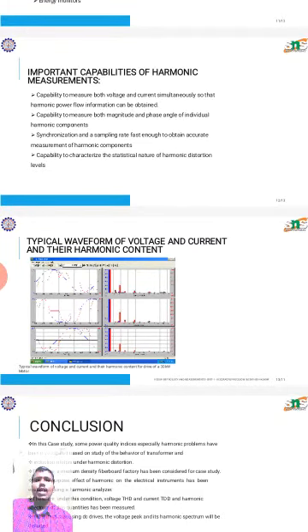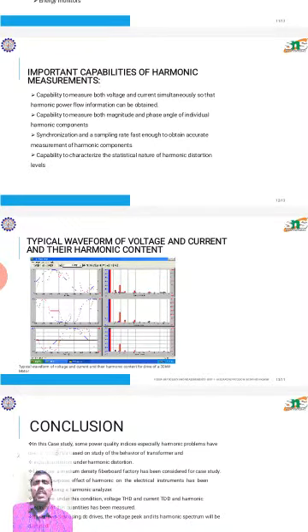So THD means the total harmonic distortion of voltage, and TDD is the total demand distortion of current. The THD and TDD of each phase have been shown in the diagrams. In addition, the magnitude of voltage harmonics, as per the harmonic distortion, causes extra losses in electrical machines, especially motors and transformers.